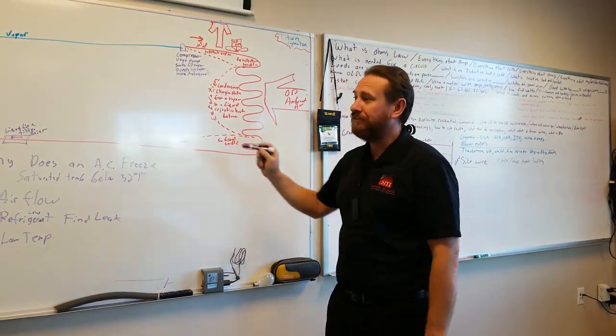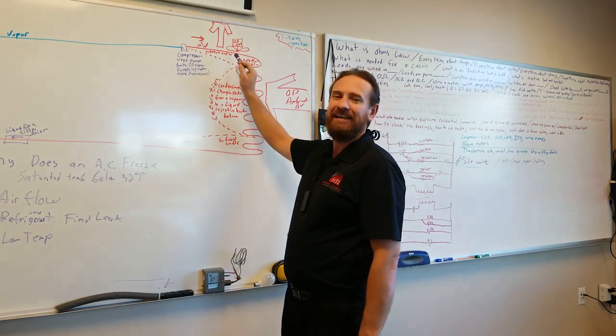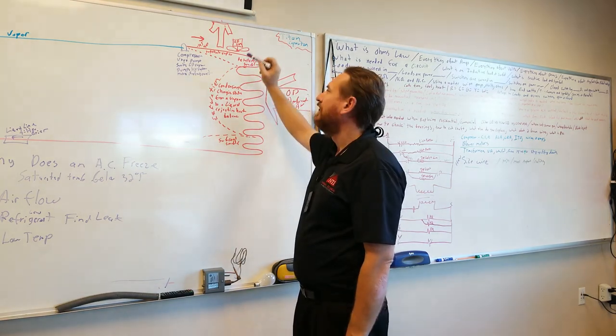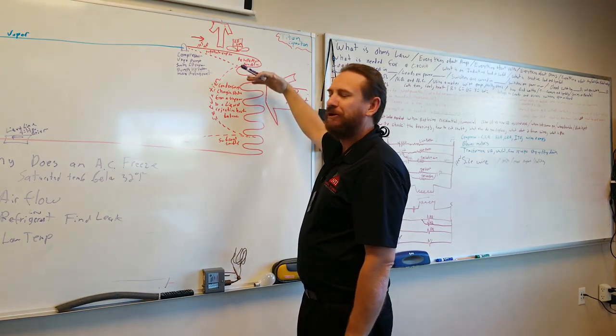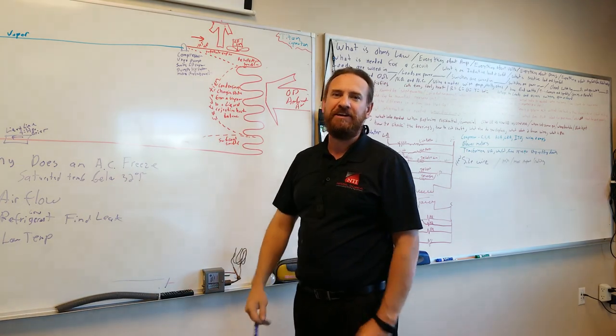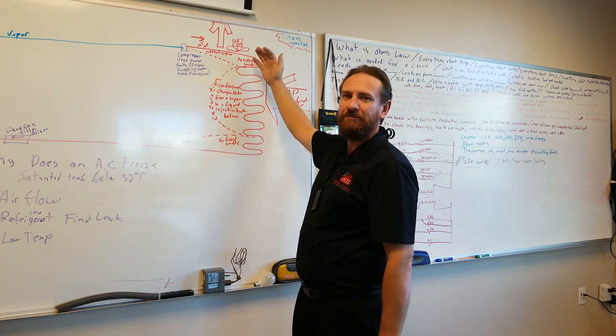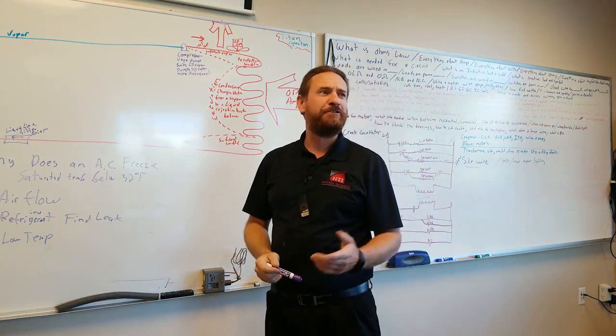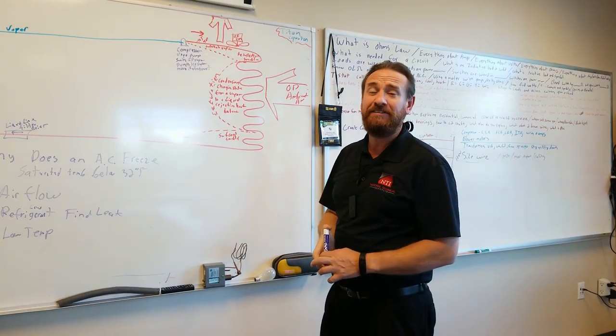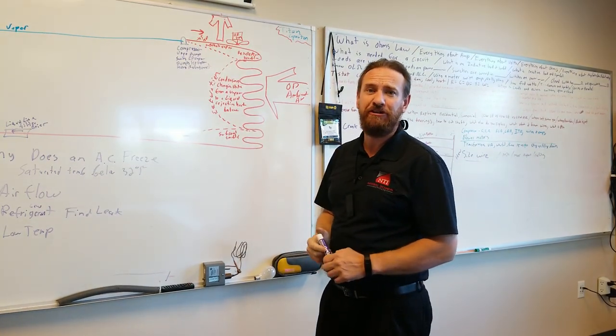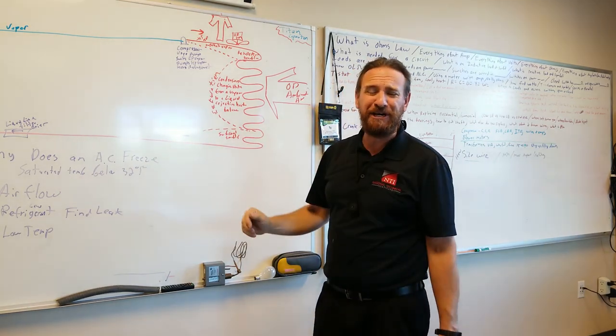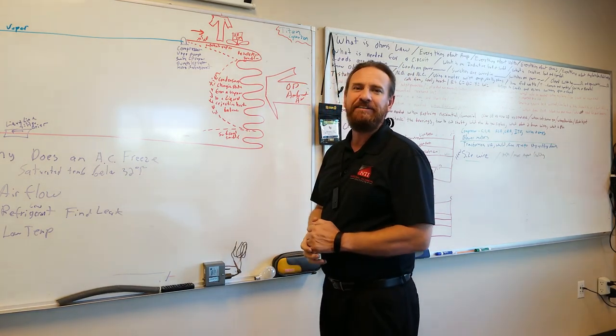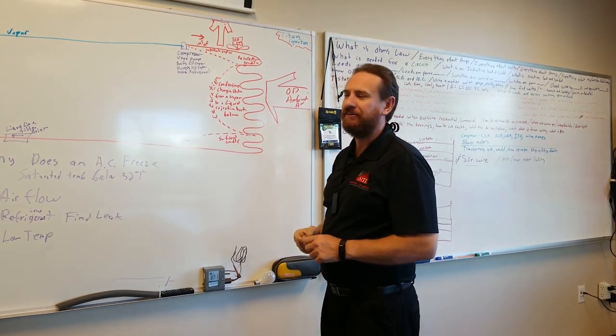There are solutions for low outdoor temperature freezing. A freestat inside will help, and you can also install a low ambient kit — a fan cycle switch. As outdoor pressure drops too low, it shuts the condenser fan motor off so pressure builds back up, then the fan comes back on when pressure reaches a set point, cycling the fan on and off to maintain head pressure. You see these in commercial buildings like airports where cooling is needed even when it's cold outside. Make sure you use bearing fan motors since the on/off cycling can wear out sleeve bearings.